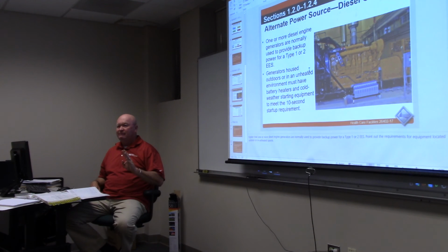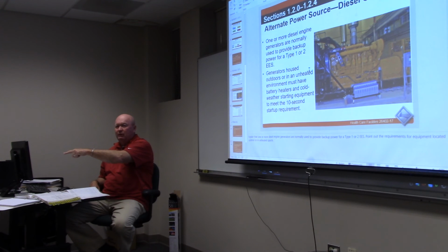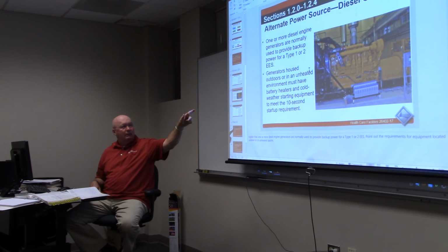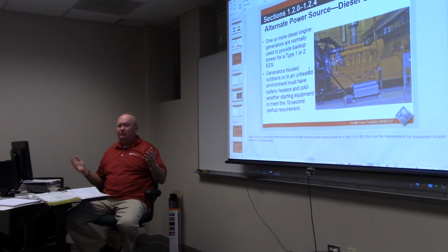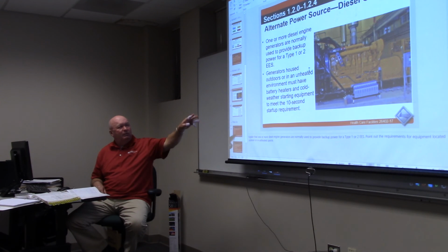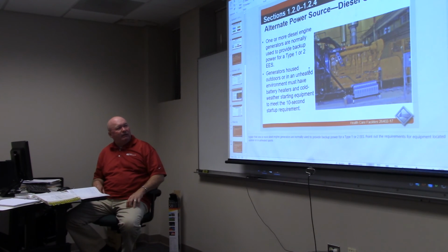I'd say a minimum of 3. You're gonna do your power, you're gonna have some type of 120 volt for your heater, a battery charger or battery heater, and then you're also probably gonna have some type of low voltage wire between the transfer switch and the actual generator. At least 3, though sometimes that's missed. So that's our generator, and that one there is actually a rather large generator, pretty big from what I see.